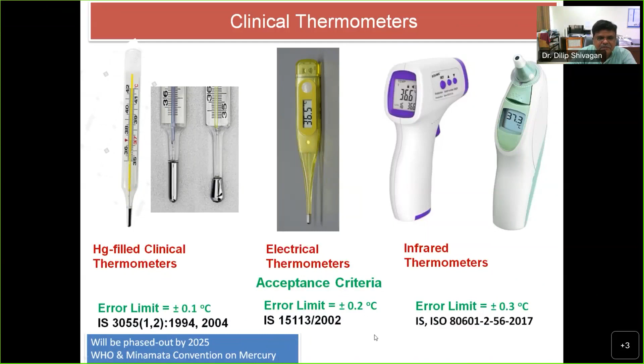So there, the new parameters will be emissivity and size of source, meaning at what different distance you have measured. These are the new parameters that you need to take care of while doing radiation pyrometry. So we thank legal metrology really. We could focus more on these clinical thermometer parameters, even for contact as well as radiation thermometry. These are the underlying standards and the given permissible limits. We have to stick to that, and we have to avoid false acceptance and false rejection.